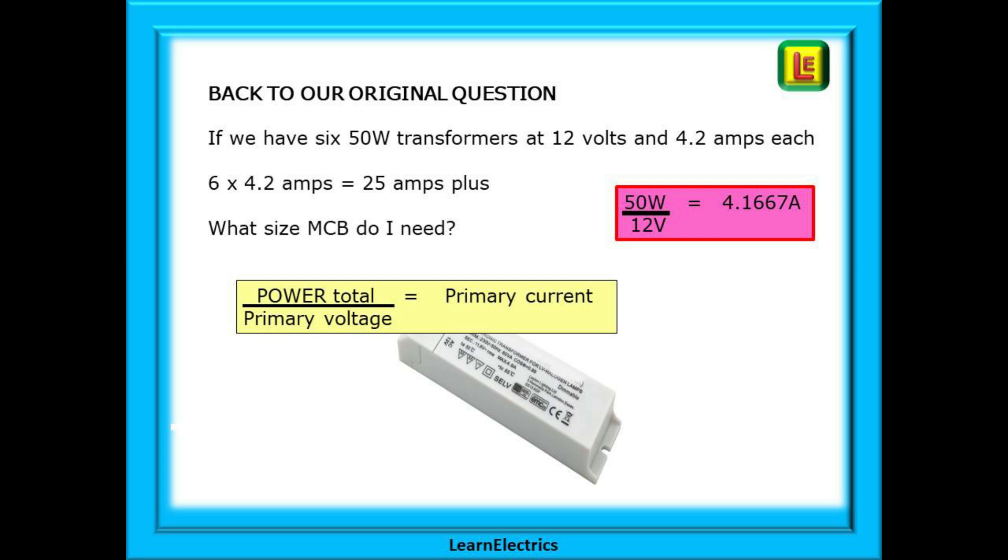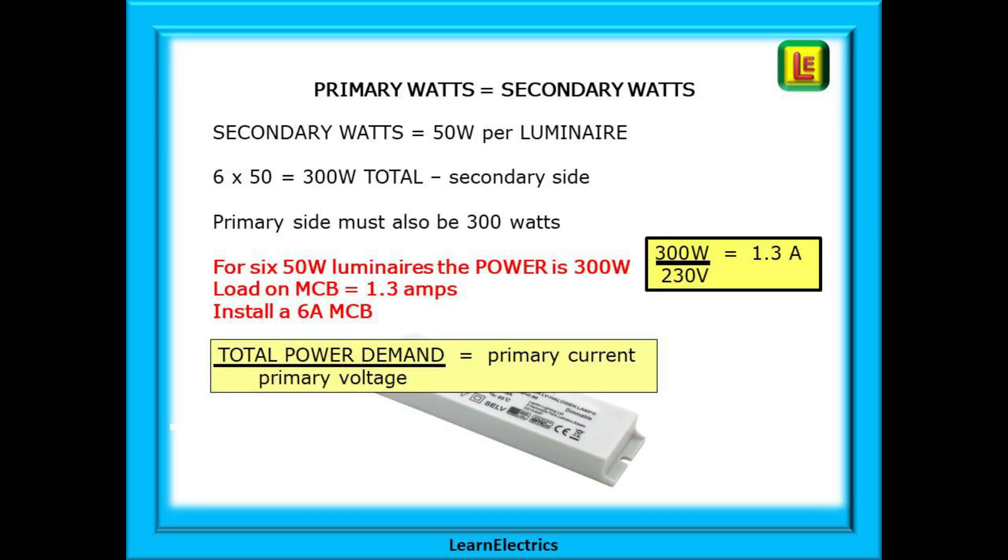Well, now we know that the power total divided by the primary voltage will give us the primary current. And if we know the primary current, we can decide on a suitable rating for the MCB in the consumer unit. On the secondary side, each luminaire is rated at 50 watts. There are six of them, so the total power is 6 times 50, or 300 watts.